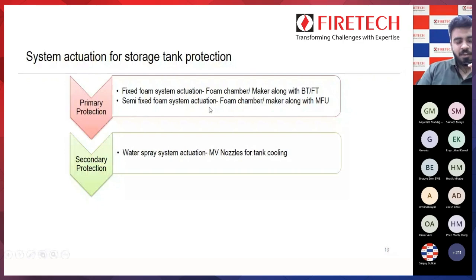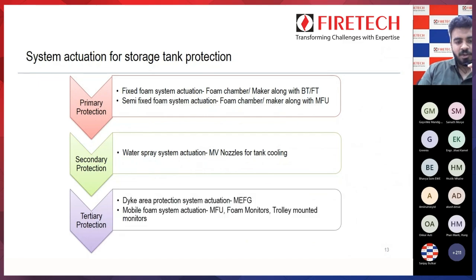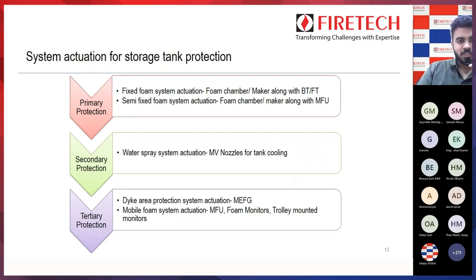For secondary protection, we have water spray system actuation using MV nozzles — it is only for tank cooling. For tertiary protection, we have dike area protection system actuation using MEFG, or mobile foam system actuation from mobile foam units which are portable, or foam monitors and trolley mounted monitors can be used. These are the three types of protection which occur one by one during a fire scenario.